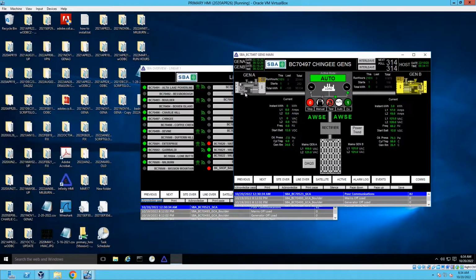We have statistics on each generator for run hours, starts, and total kilowatt hours produced for overall totals, today and yesterday. The same is reciprocated on generator B on the other side of the page. The transfer switch senses the instant power in kilowatts, current in amperes, voltages in volts AC, as well as frequency in hertz. If any of these analog meter devices falls outside of the normal operating range, this indicator will go dark, and the load will be released.